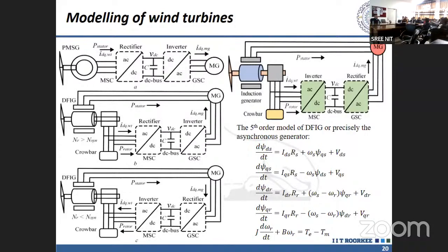Power can be extracted from both rotor side and stator side. Here you require a prime mover which is rotating. So your rotor and stator both are 3-phase windings. On the rotor side, it can supply power as well as absorb power. That will depend, but from the stator side, this is always supplying the power.